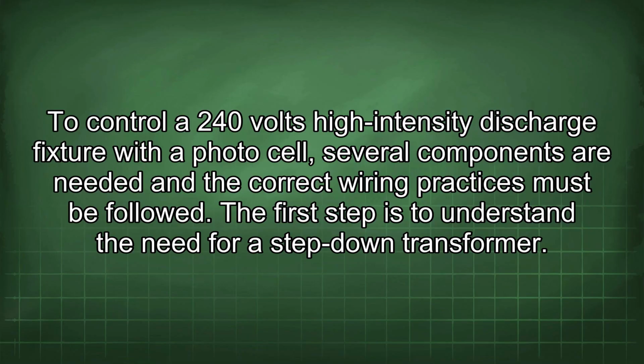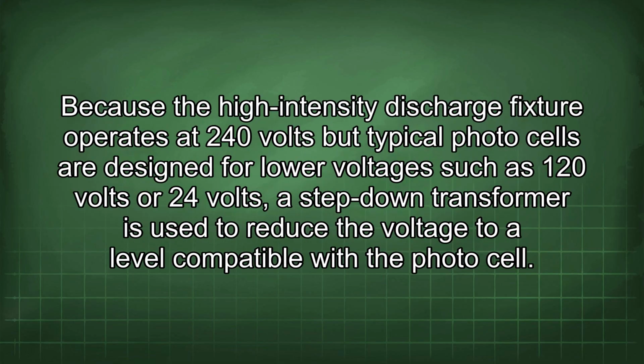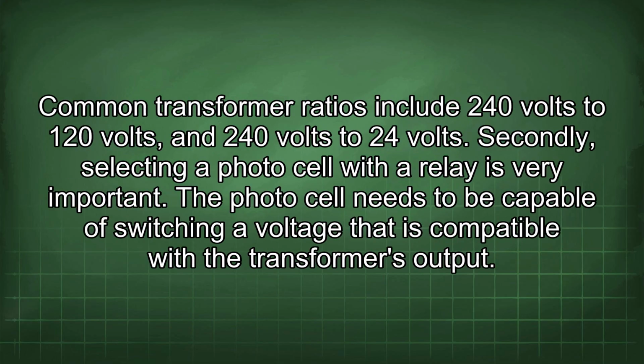To control a 240 volts high-intensity discharge fixture with a photocell, several components are needed and the correct wiring practices must be followed. The first step is to understand the need for a step-down transformer. Because the high-intensity discharge fixture operates at 240 volts, but typical photocells are designed for lower voltages such as 120 volts or 24 volts, a step-down transformer is used to reduce the voltage to a level compatible with the photocell. Common transformer ratios include 240 volts to 120 volts and 240 volts to 24 volts.